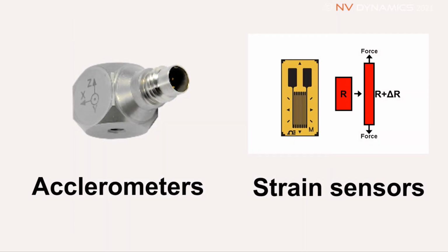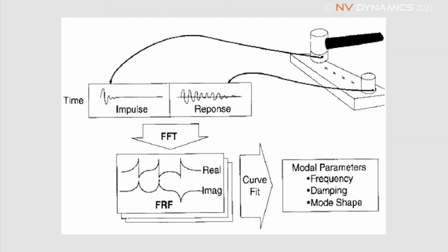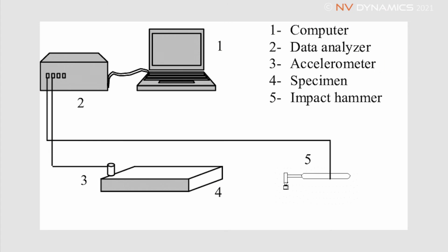Two traditional methods exist to conduct a system response testing. The more commonly used method is to use an instrumented hammer as an input device, and the outputs of vibration response are measured using accelerometers and other vibration or sometimes strain sensors. This method and approach works well when the device under test is smaller and rigid enough. Test methods like roving force or roving response approaches are used based on the instrumentation resource availability.